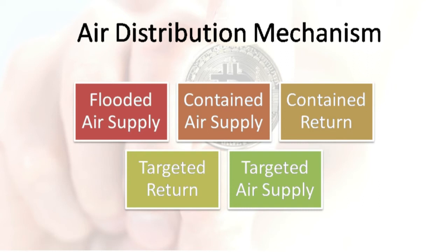The answer of which architecture to choose is relatively straightforward. That is, the more control you put over the air and movement, the higher the solution's cost will be. So you will always need to balance what is more important, whether the flow of air or the cost that you will pay. If you're thinking about this for a long-term approach for a large-scale mining farm, I would recommend at least the targeted supply architecture, just so it has a more controlled and efficient air circulating environment.